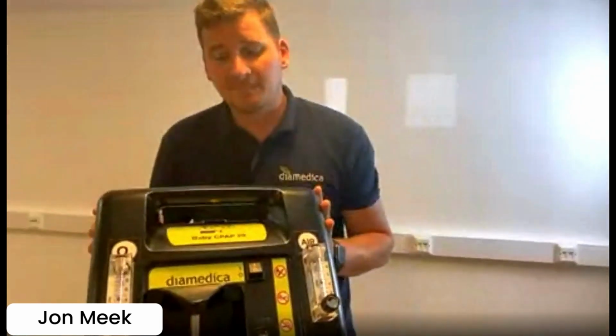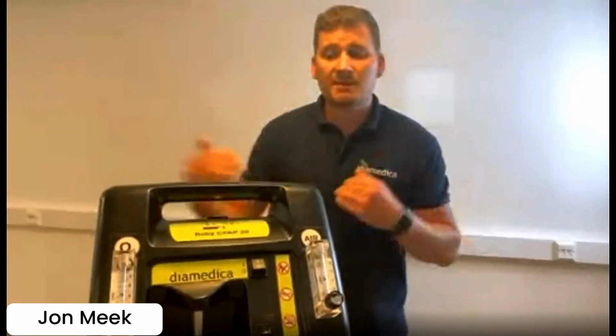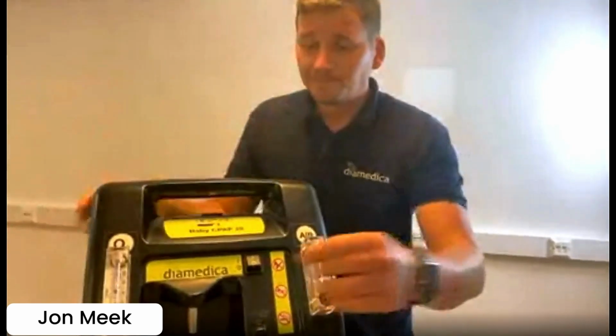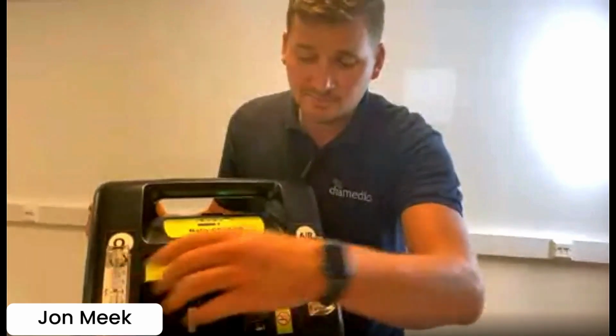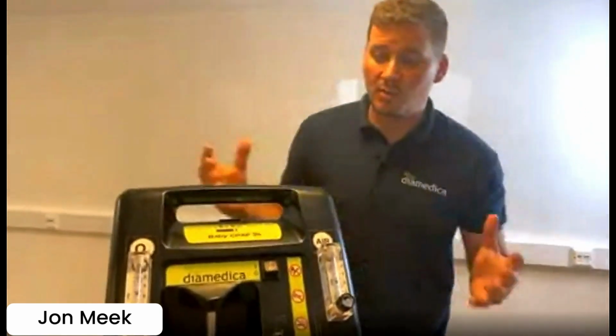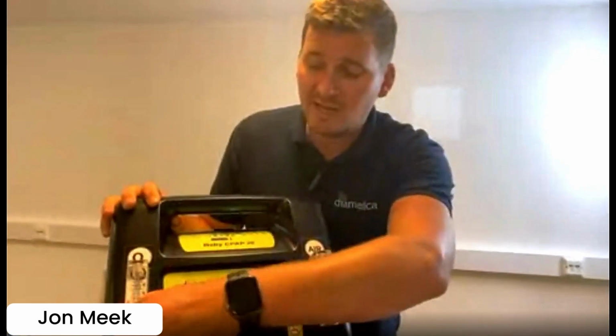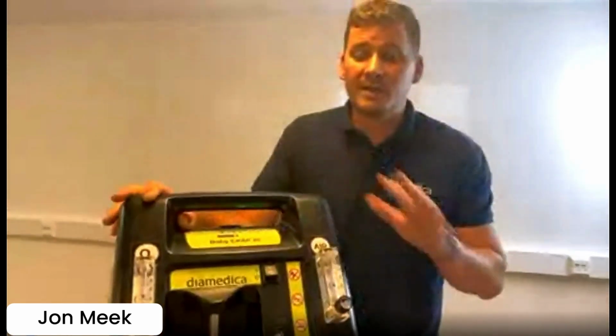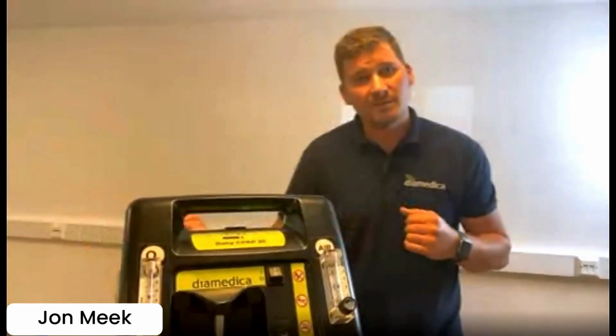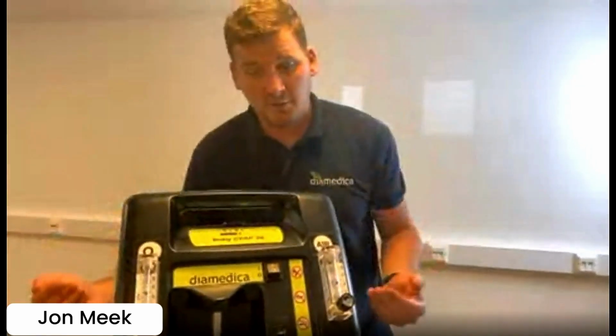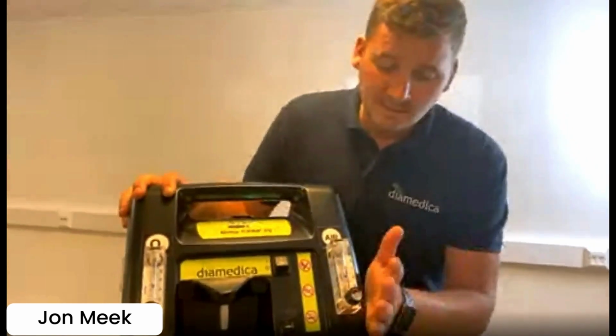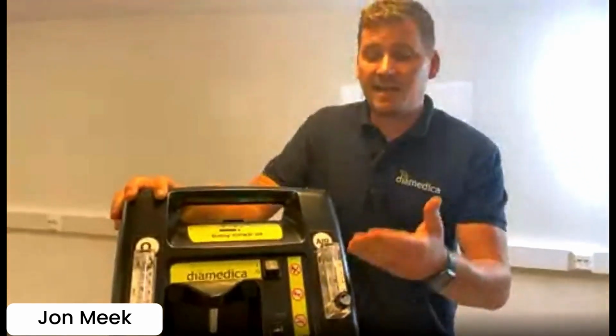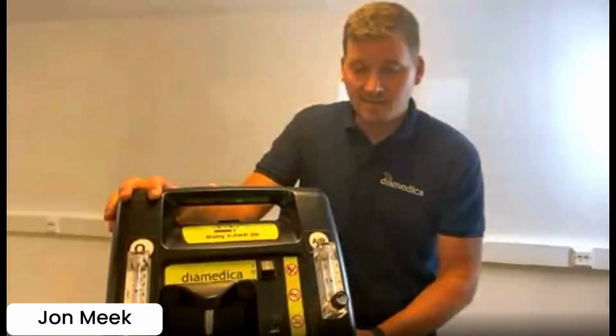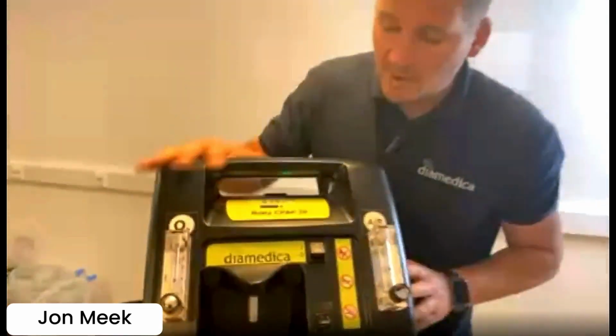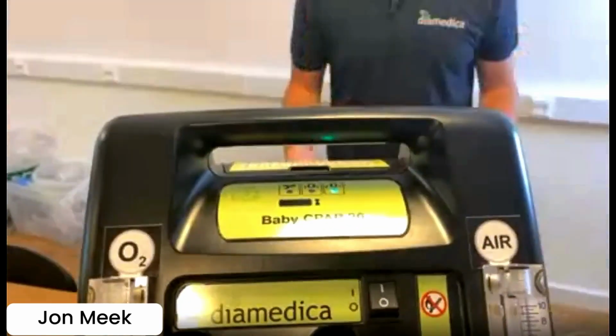The sieve bed should not need replacing at least up until 5, maybe 10,000 hours, depending on the liters per minute used. If you overuse the oxygen, you will deteriorate the sieve beds a lot faster. And that's one of the biggest pickups that I come across myself. That people think you need high flows above and beyond 10, when it's not that that's generating the CPAP, it's the pressure, which I'll show you in a minute. These are just creating the oxygen air mix at the flow required. Same on the air. Please don't exceed 10 litres a minute. It's there and designed to run 10 litres a minute as a maximum. As you can see, that was quite quick. The green light has now come on, which means she is safe to use.